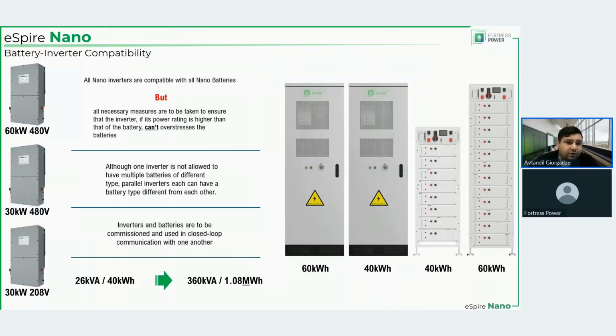Now, all nano inverters are compatible with all nano batteries. So for example, you can have, I don't know, a 60 kilowatt 480 volt inverter with a 40 kilowatt hour indoor unit, or outdoor unit for that matter. But all necessary measures are to be taken to ensure that the inverter cannot overload the battery. So these batteries are rated at 1C discharge. So the maximum continuous power that 40 kilowatt hour units can handle is 40 kilowatts. So either with inverter settings or with overcurrent protection devices or both, you need to limit how much power the 60 kilowatt inverter unit can extract from the 40 kilowatt hour battery unit or deliver to it.